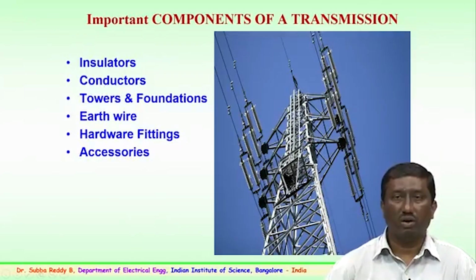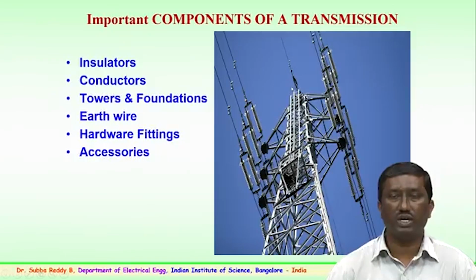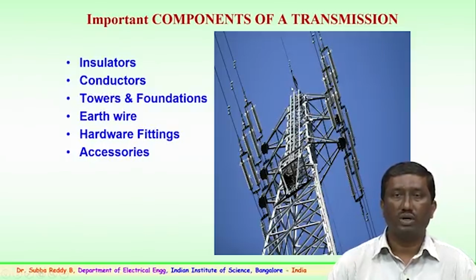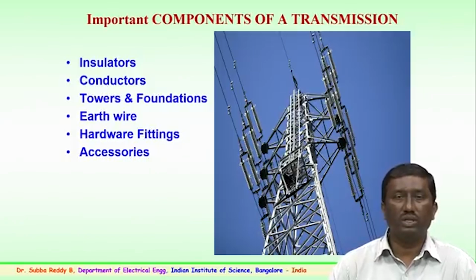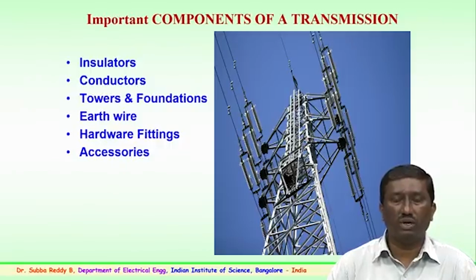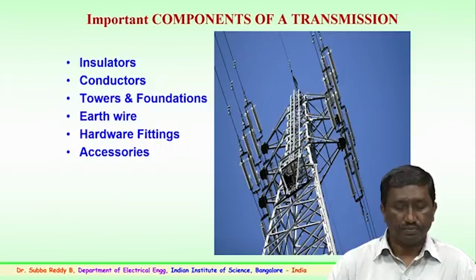The earth wire is shown here. This is the earth wire which is connected to the topmost portion of any EHV or UHV transmission tower. In case of lightning, this has to protect equipment like the insulator strings and further the substation components. So, the earth wire or ground wire plays an important role, particularly during lightning strikes on long high voltage transmission systems.